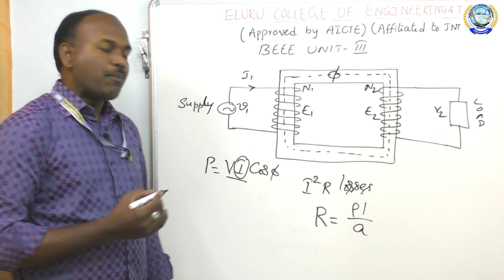So there is only one choice: to reduce the current value. In what way? P is equal to V into I into cos phi, this is our formula for AC power. So you are in a position to change the voltage and current values: the current value reduces by increasing the voltage value. Here I am indicating N1 turns on the primary side and N2 turns on the secondary side. So one important point is EMF per turn.